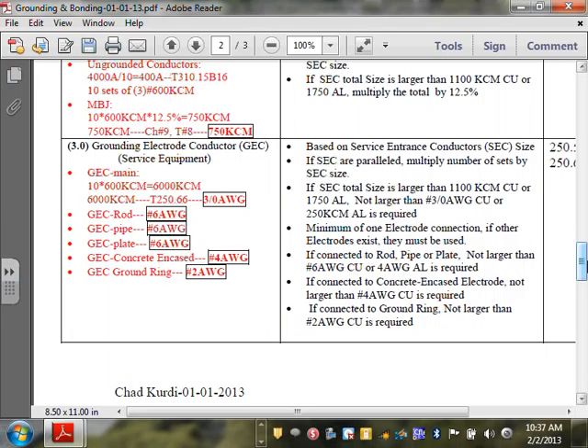So the wires, it's an isolated ground wire, an isolated ground all the way to the service. Supplemental ground. Yeah. So you're going to ground these two systems, and also the other part that's going to be part of your grounding system is going to be your lightning protection, if any. Lightning protection for the whole building could be bonded all together because it's a grounding electrode system. So all this together has to provide a low impedance to the ground. A low impedance to the ground.